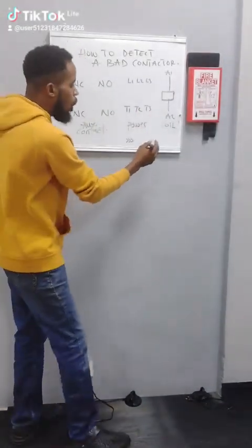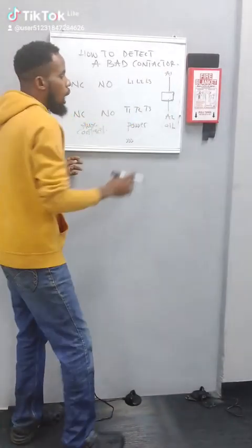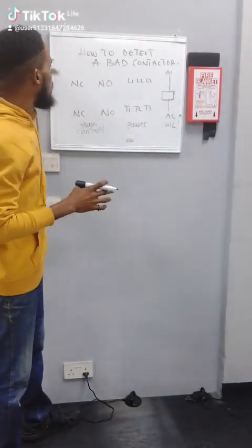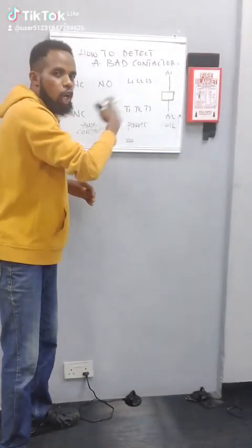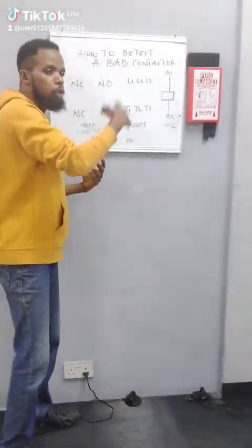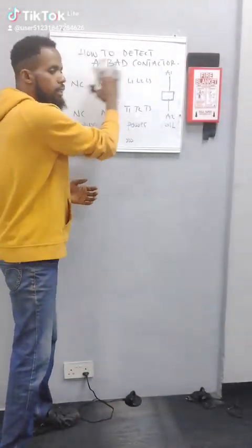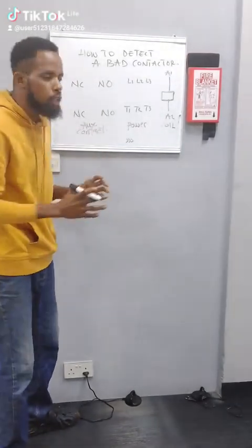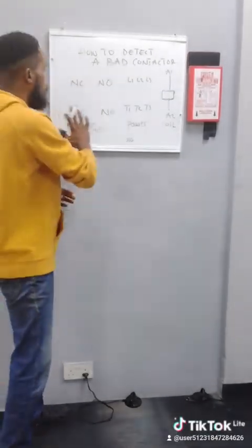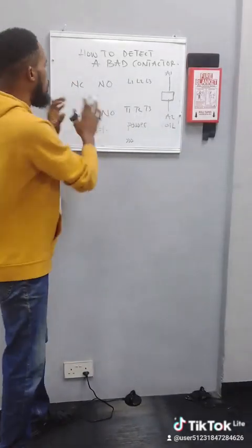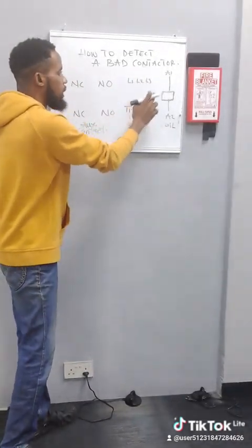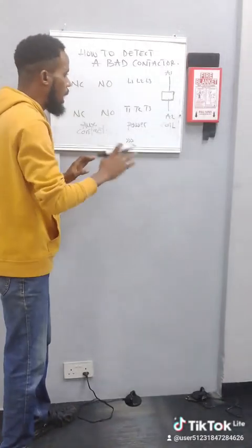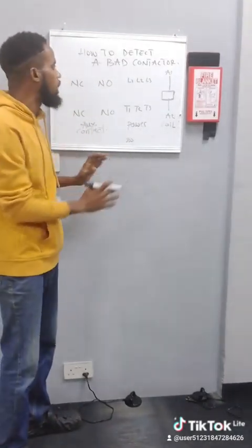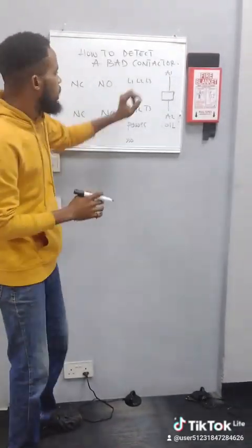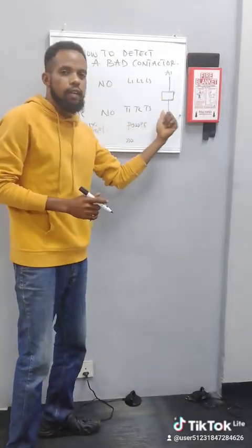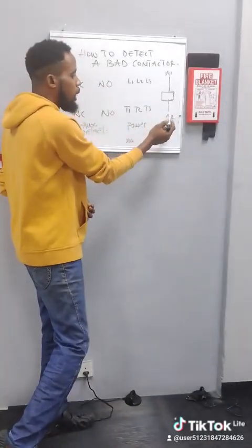When you check the continuity, you check the resistance, the ohms. At the time you are checking the contactor, disconnect all the power entering the contactor, the input power. There should not be power in the circuit at all. That is the first step. Switch off all the circuit breakers before you do your troubleshooting. Then the first thing you check is the resistance from the A1 point to the A2 point.